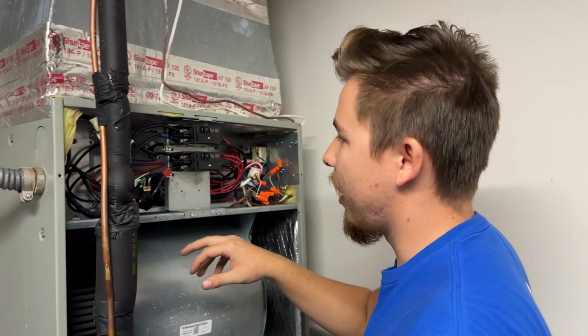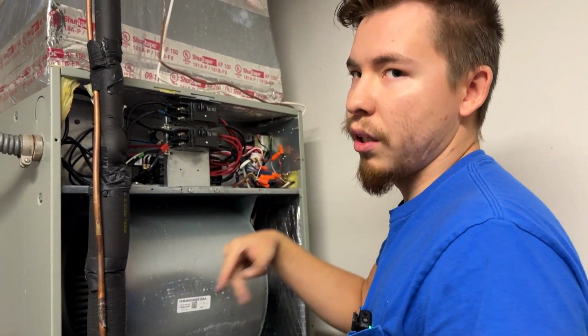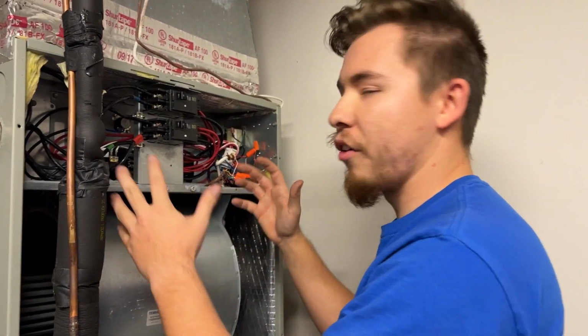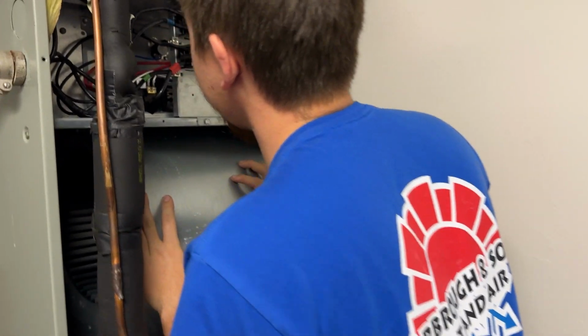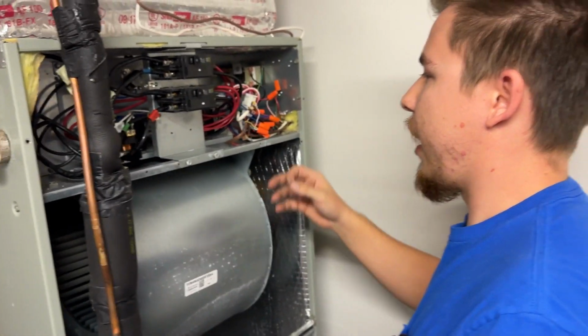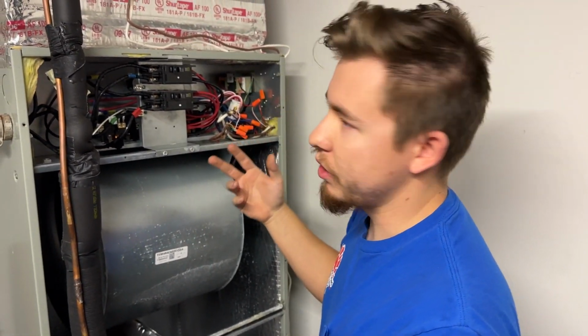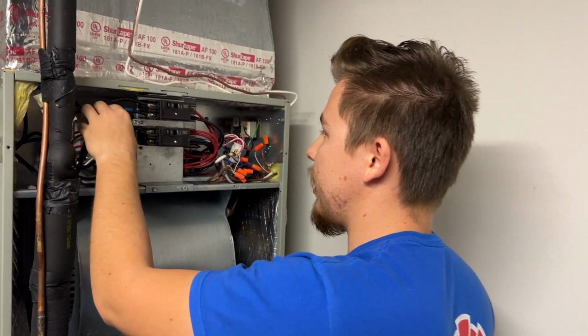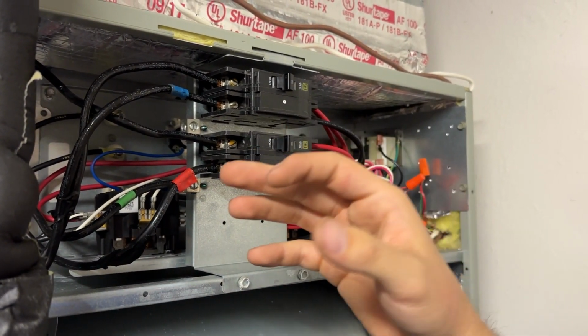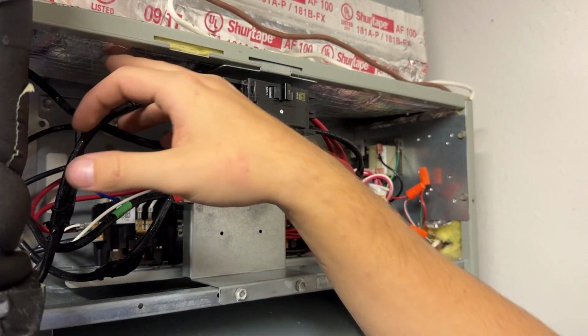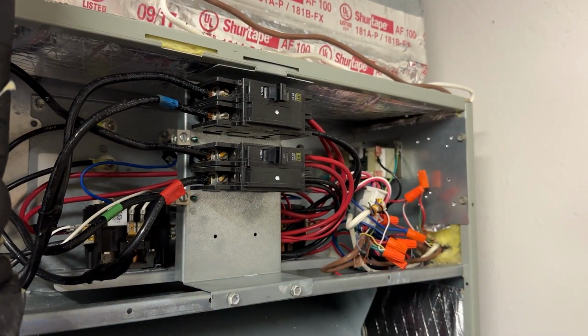After it goes to the high limit, it'll go to your sequencer. After it hits your sequencer, it's kind of hard for me to show you what it does or where it is, but after it goes to your sequencer, it'll come back to your breaker to complete one circuit. This is the easier way to test our heat strips. It's kind of color coordinated. There's two 60 amp breakers. I'm going to keep this unit on real quick, and we're going to test these heat strips.